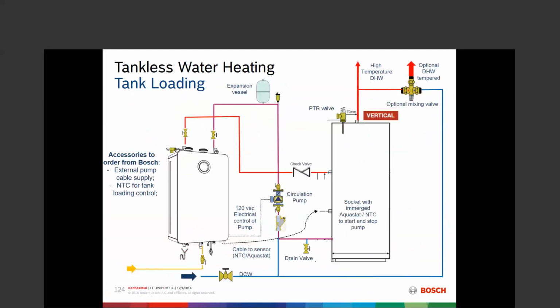We can also do the idea of tank loading, and we can do that using the controls for recirculation that are built in to the water heater itself. And this is the idea of creating a stored amount of hot water in a sealed tank where we don't have a stack loss or anything like that. So we have a very low standby loss. And what that allows for is high dump loads, and recharging that tank with basically what becomes a sidearm.